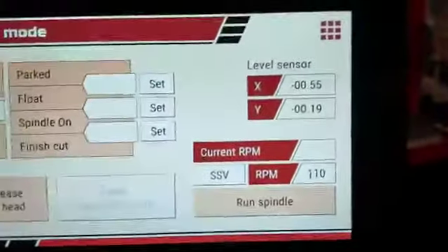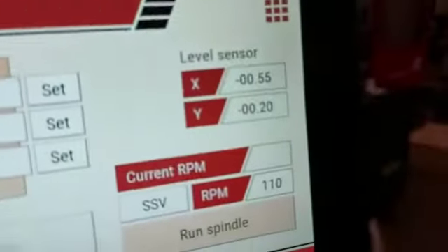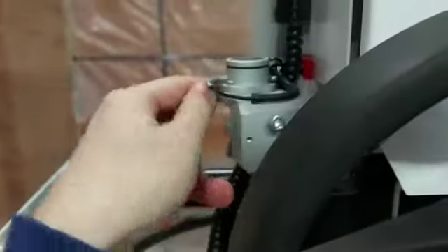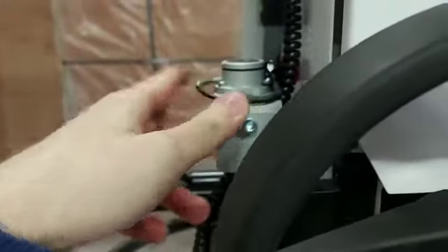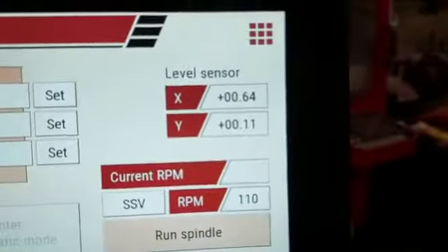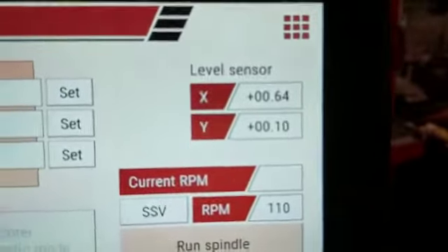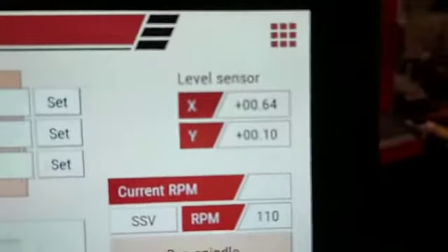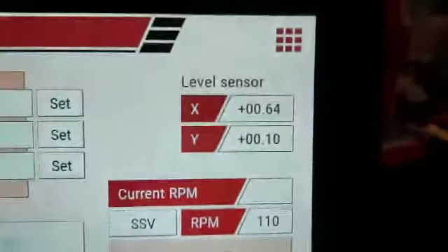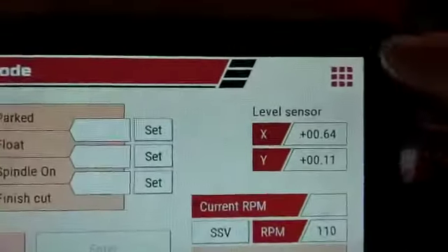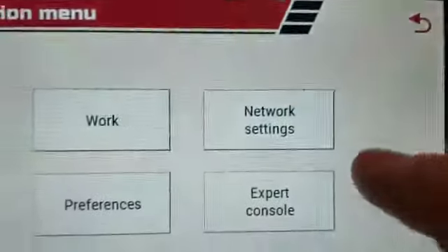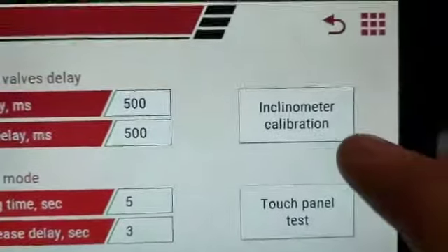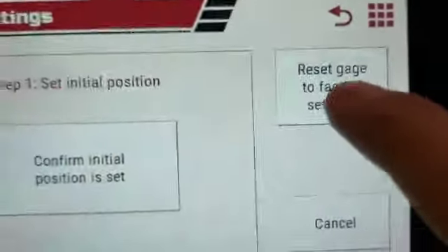So to check whether it needs calibration, you should take a look at the values stated here, and then turn it 180 degrees around its axis. Now you should expect the values to be the same, but because it's not calibrated, it's slightly different. So it was 0.55 for the X, and now it's 0.64. So in order to calibrate the inclinometer, you need to go back into the menu and go into Expert Console, where you'll find the inclinometer calibration button.